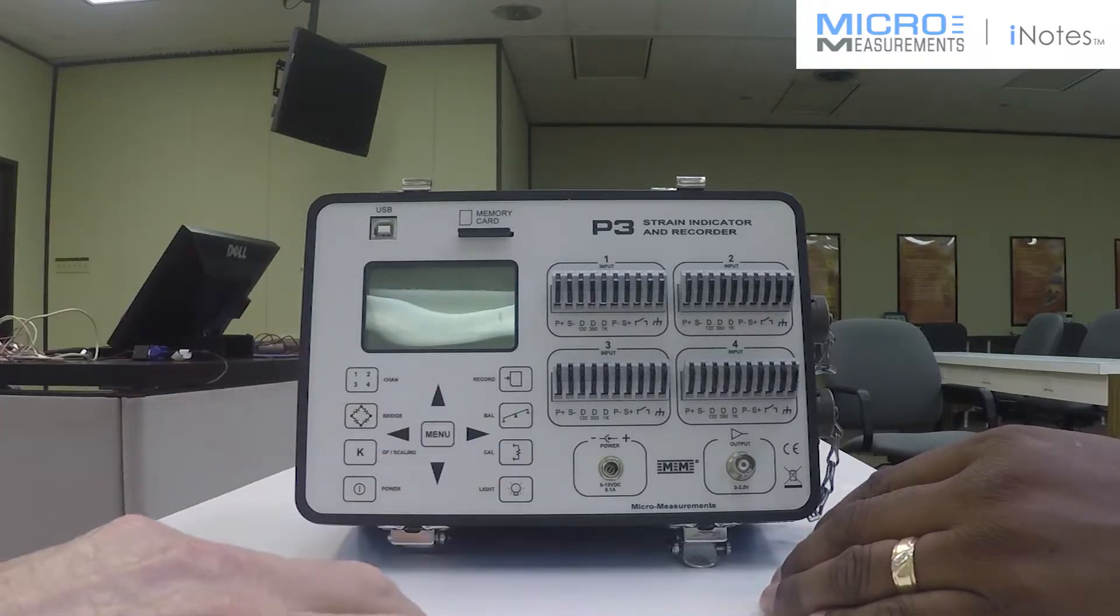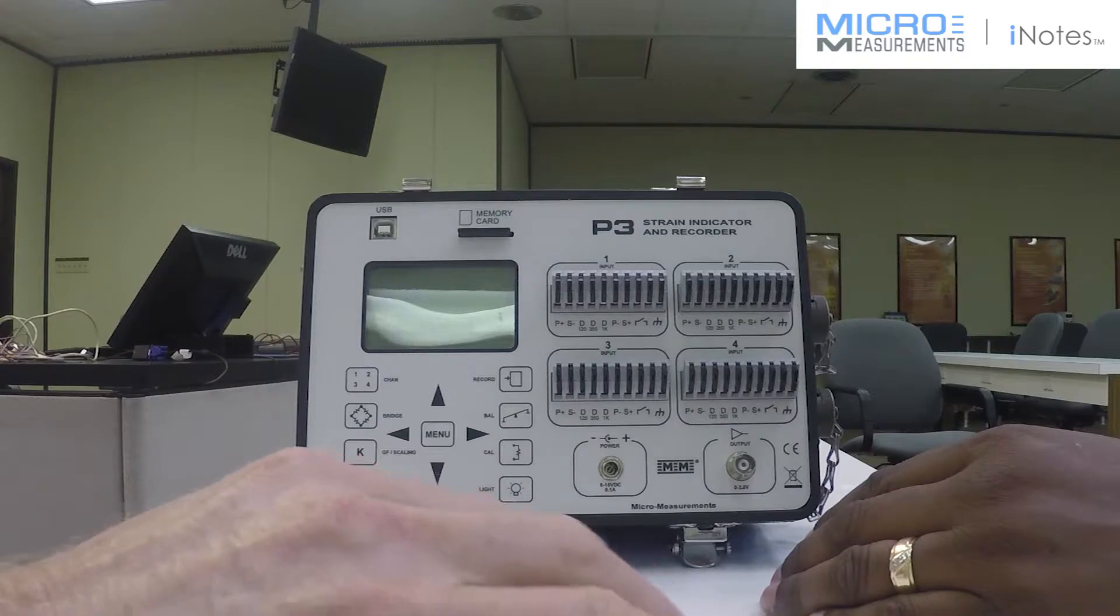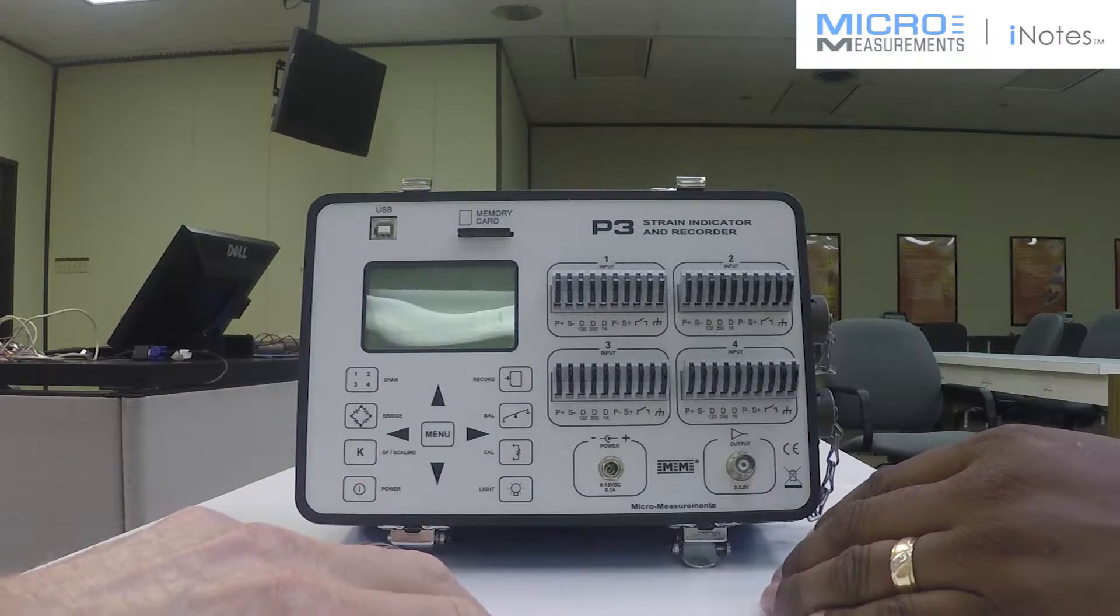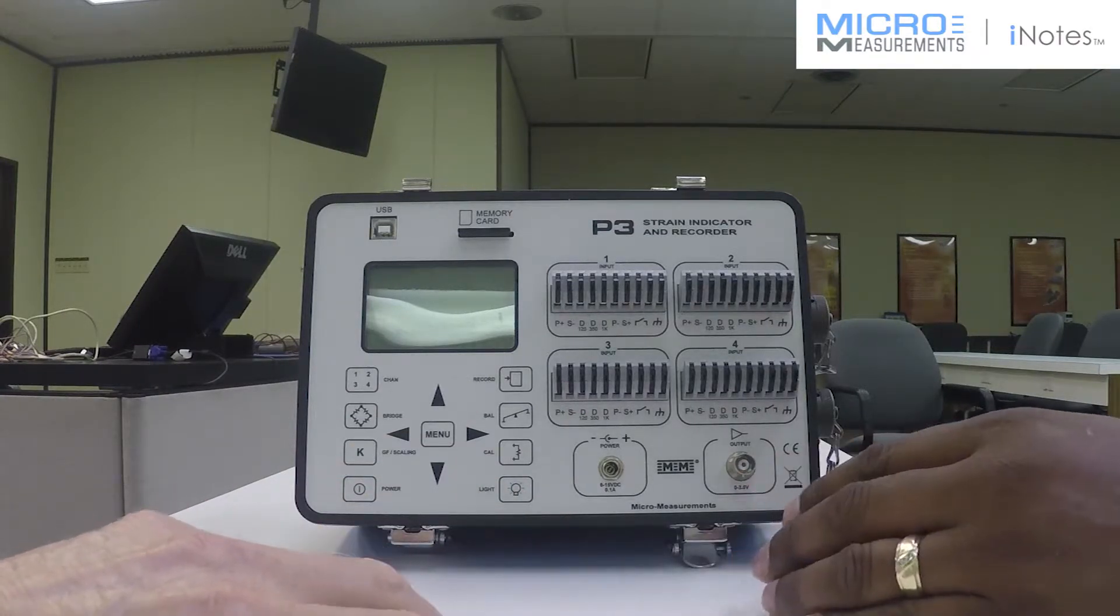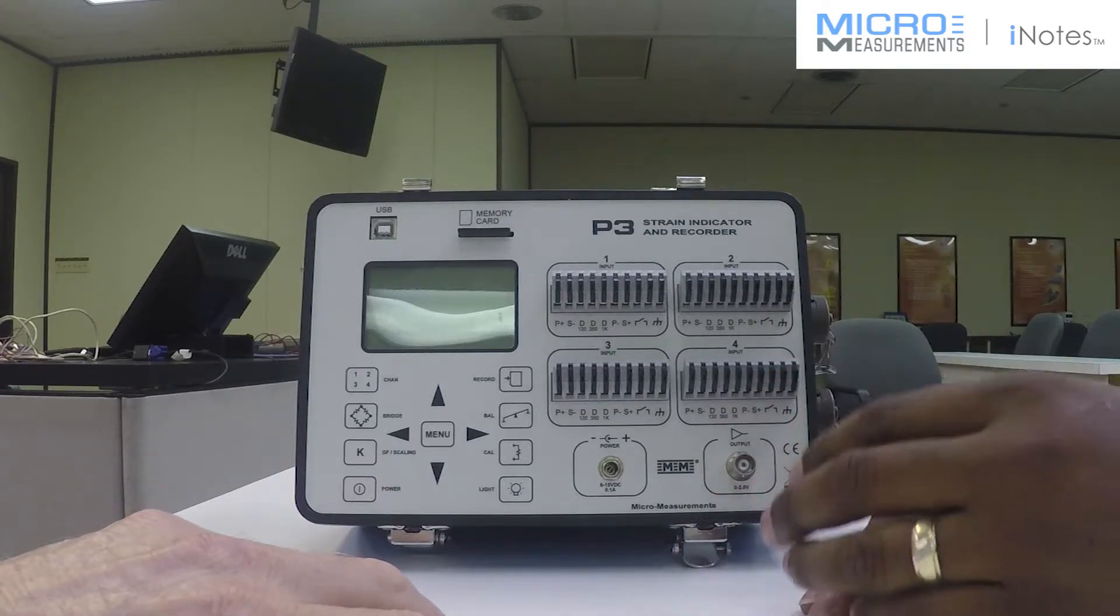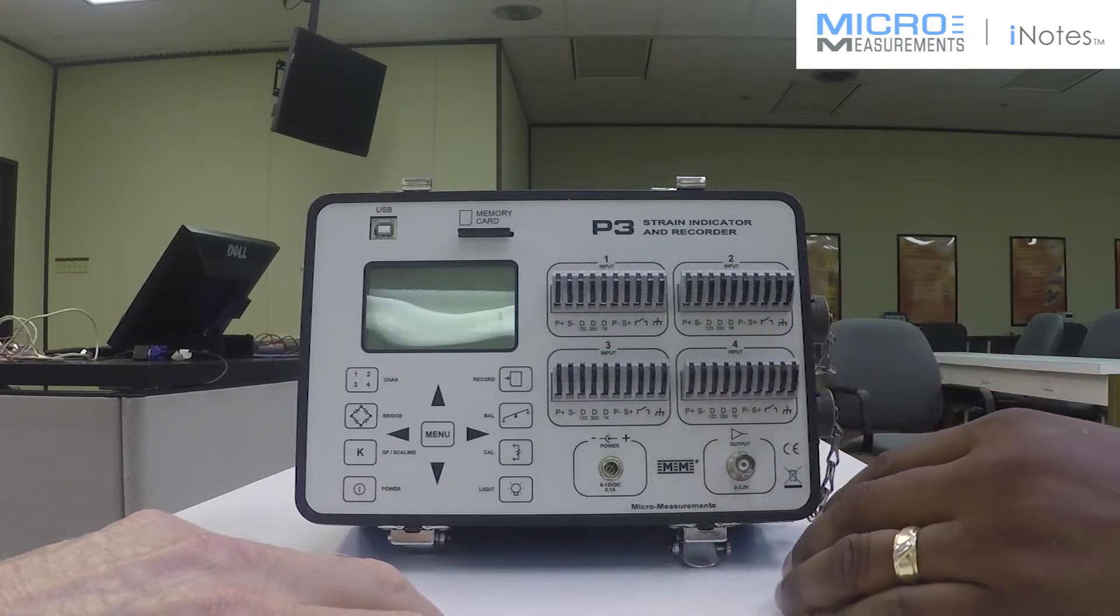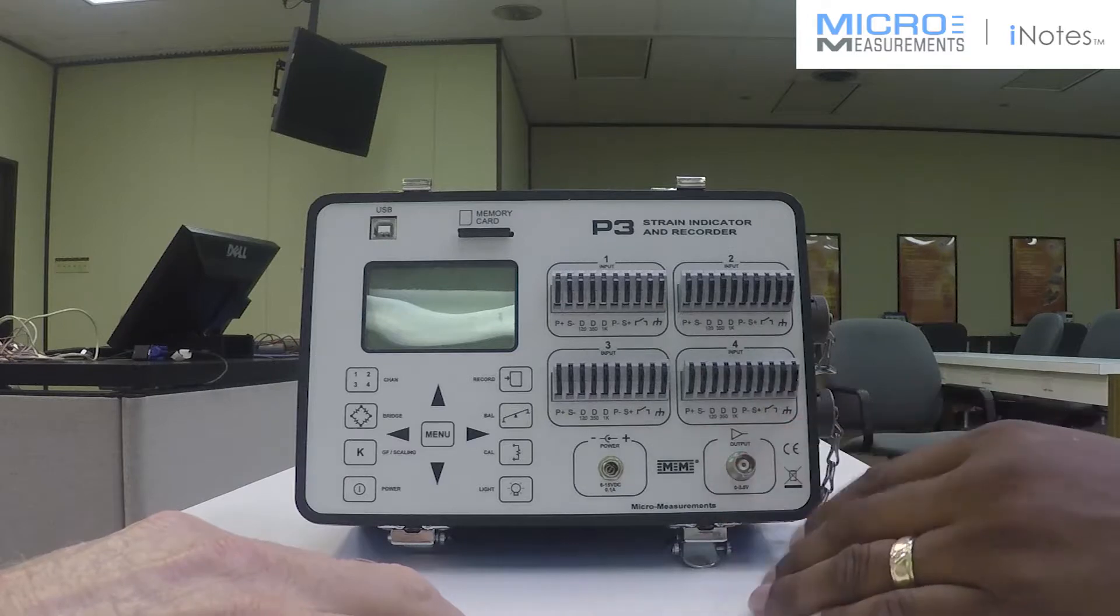I don't see any knobs or adjustments for doing, say, balance or calibration. How is that handled? Well, the system does an auto calibration built in, so there are no pots to adjust to zero out the offset. It's all done internal to the box.